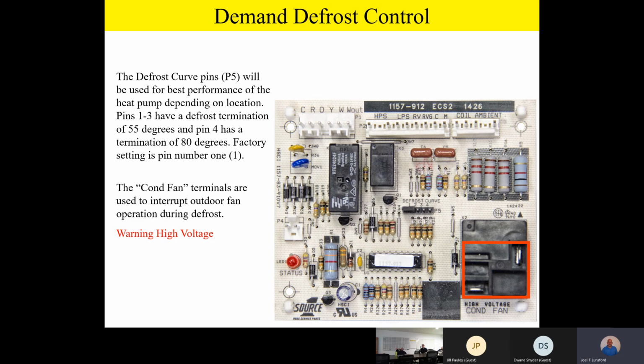All we're doing is breaking one side of the condenser fan motor. And of course, that condenser fan motor, based on the product, could be up to 230 volt. We're just breaking one side, so you could have basically 110 volt to ground on these terminals. So please be careful from a service standpoint.